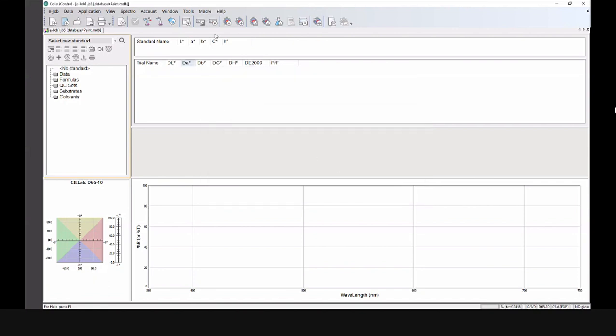So once we do calibration measurement, then standard or trial measurement is the same as we do in reflectance mode. First we measure the standard, then we measure the trial, and then we check the delta value as well. This measurement is the same, but to understand, we are placing the sample near the aperture side, outer near the sample port, but in liquid measurement we have to keep the solution or material inside the kit. That we will see in the further video.